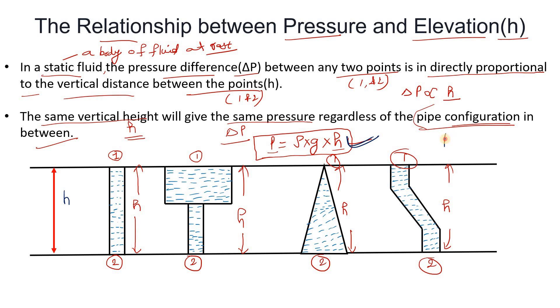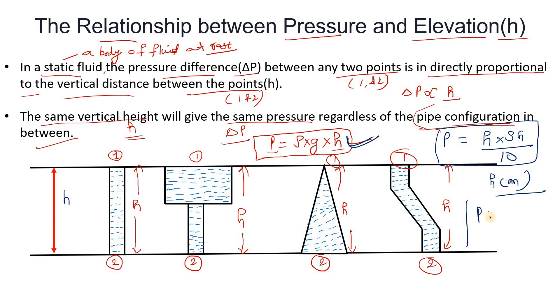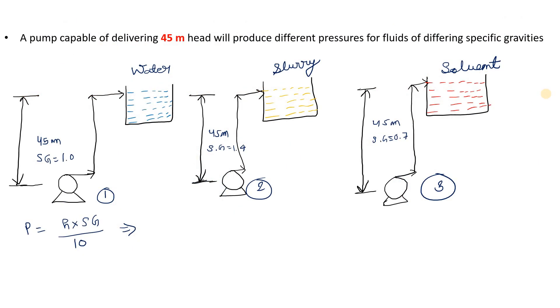There is also another formula to find static pressure: p equals h times specific gravity divided by 10. You use this formula when your head is in meters and the pressure unit will be bar. When your head is in feet, the formula is: p equals feet times specific gravity divided by 2.31, and the pressure unit will be psi.